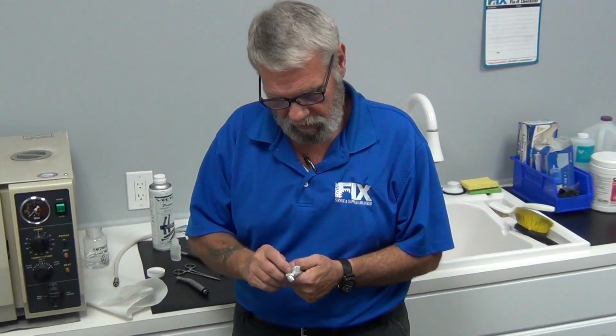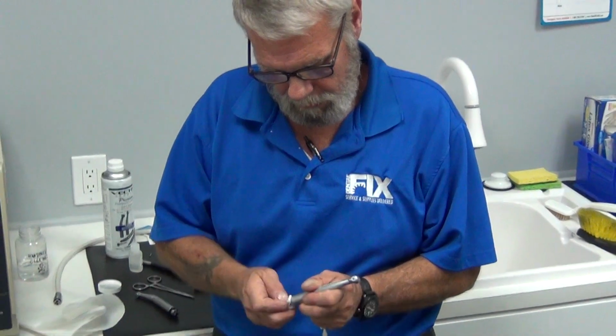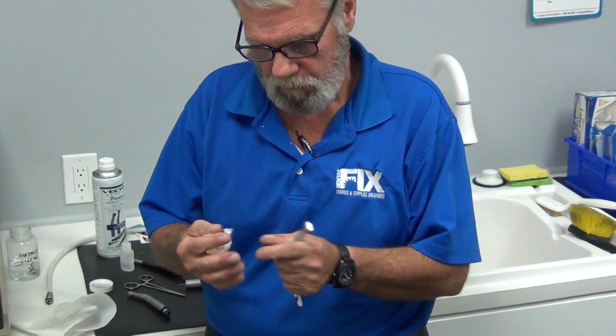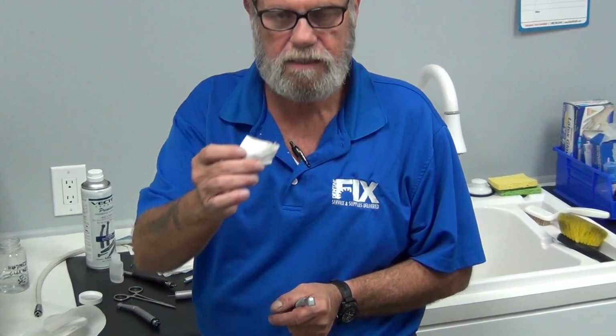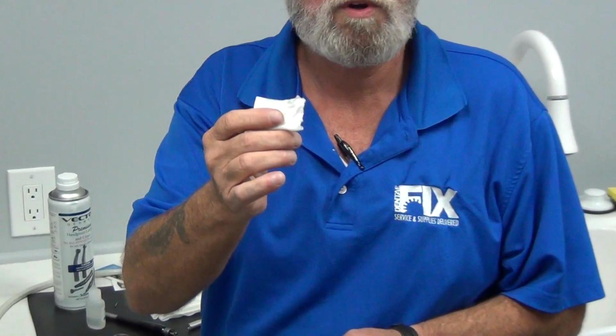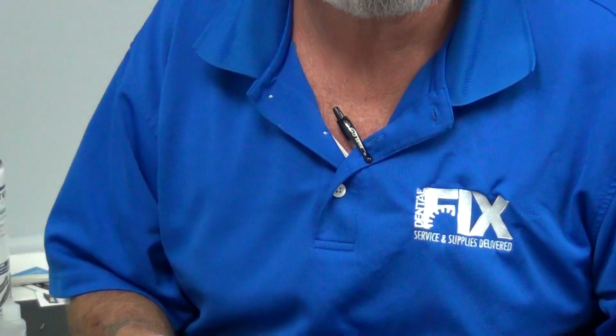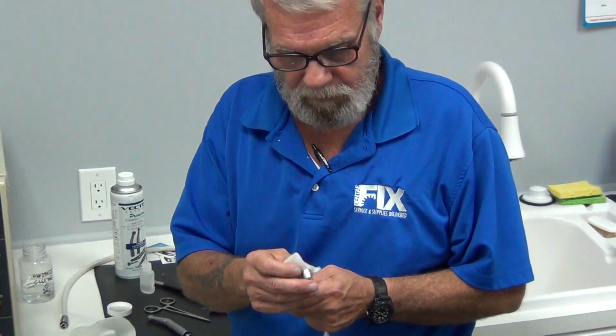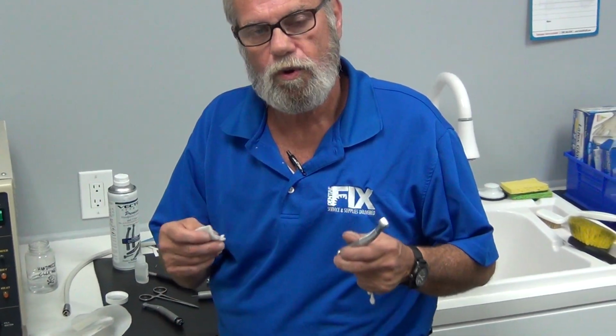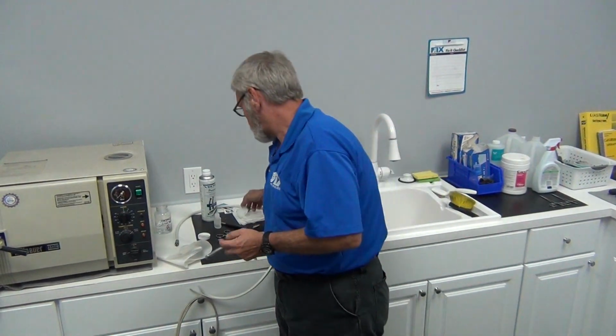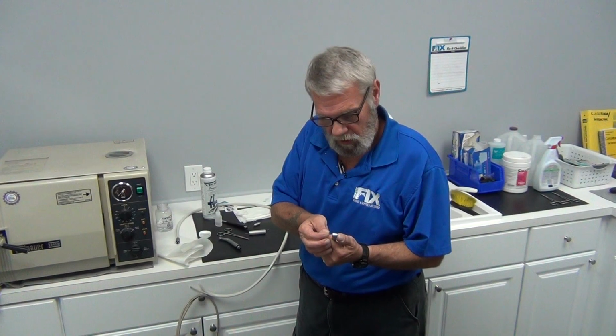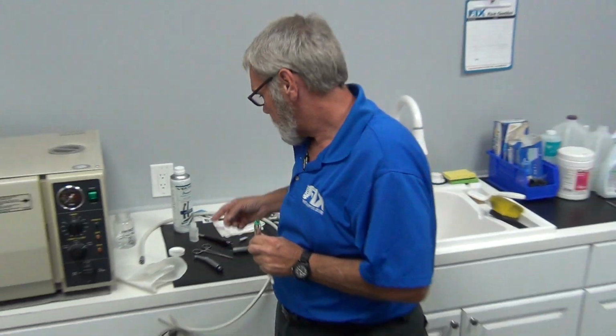So, we've given it a nice thorough wiping. Even the tubes. And just look what we've got off the handpiece. A lot of debris. Basically it's oil grime. When they're wiping it after real use in an operatory, they'll have blood, they'll have detritus and debris on it, coagulant. So we've got the handpiece externally clean. Now we're worried about the running of the handpiece, okay? Now we're worried about lubrication, purging, and running. We're going to put our burr or our slug back in the handpiece. And we are actually going to show a couple of different ways of lube.